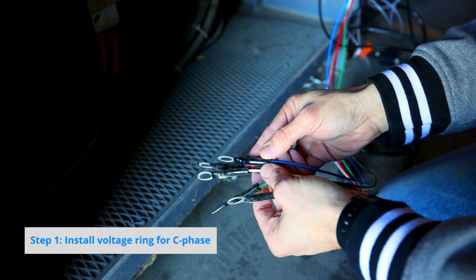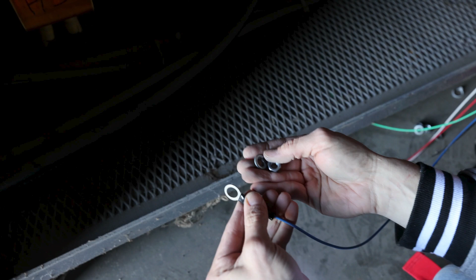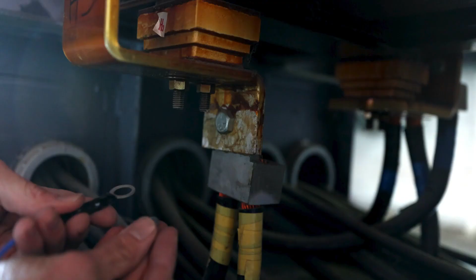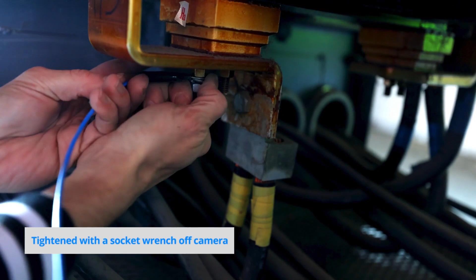First, I'm installing the voltage ring for C-phase in this transformer. That consists of a bolt and a lock washer here so it doesn't come off. C-phase on this transformer monitor is blue in color, so you see the blue ring going on the H3 bus bar here. Next, we're installing the rings on B-phase.